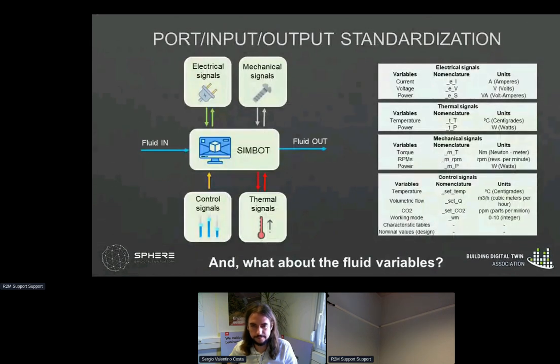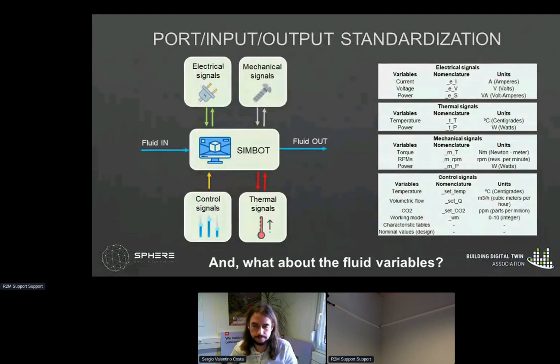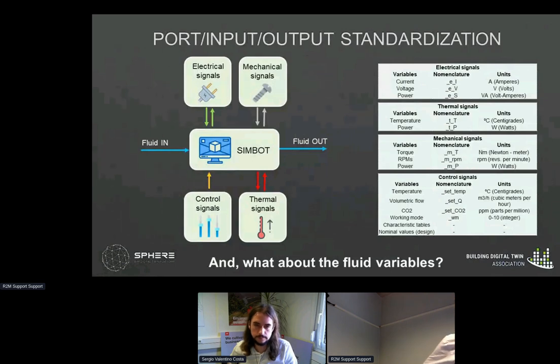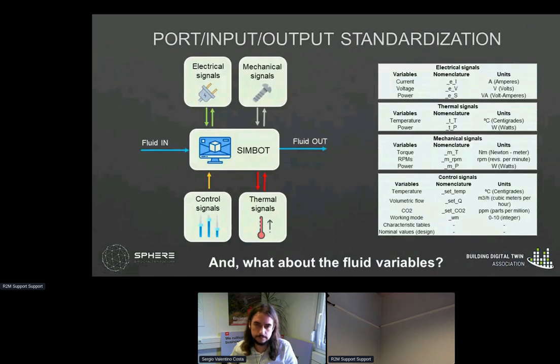Typically, SIMBOTs will have different categories of inputs and outputs: electrical signals, thermal signals, mechanical signals, control signals, and fluid variables. A common or standard nomenclature must be determined to properly define and understand the variables being used and exchanged. Electrical signals will take into account electrical current, voltage, and power consumption or generation. For thermal signals, temperature and thermal power can be used as inputs and outputs. For mechanical signals, torque and RPM will be exchanged in addition to power consumption or generation. For control signals, set points for temperature, volumetric flow, or CO2 concentration are provided, together with working mode, characteristic tables, or curves in different nominal or design values of the equipment.